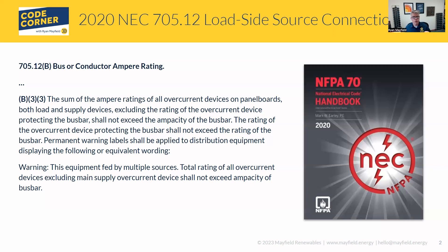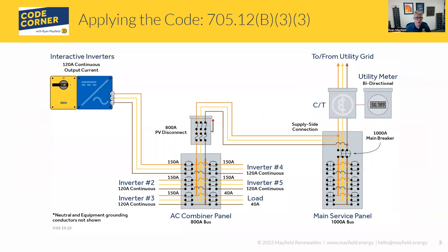And what the code says — this is a little different than B31 and B32 — in the sense that when we're adding all of our different breakers, in this case we're using the rating of the breaker. We're not using the rating of the system output. It's the rating of the breakers that dictates this calculation. So you see that language here: the rating of the overcurrent device protecting the bus bar shall not exceed the rating of the bus bar. So this is both loads and sources. So let's go ahead and take a look at a picture here.